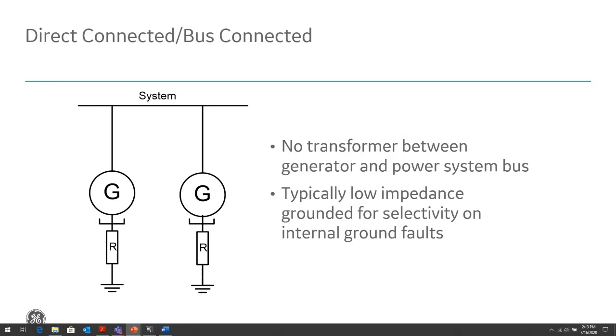How do we connect the generators to our system? One of the most basic is the direct connected or bus connected system. This example is showing two generators connected to our bus and to each other through that bus. This is typically seen in industrial, commercial, and isolated systems, not so much on the utility side or with larger generators. It's simple and inexpensive.